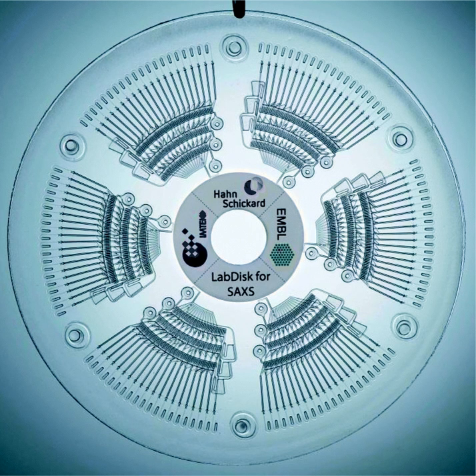Topic. Volume metering. Volume metering is a typical function of centrifugal fluidics to reach a certain amount of liquid reagent. It can be achieved by simply connecting an overflow channel to the chamber. Once the liquid is at the level of the overflow channel, the rest of the liquid will be routed into the waste chamber connected to the overflow channel.